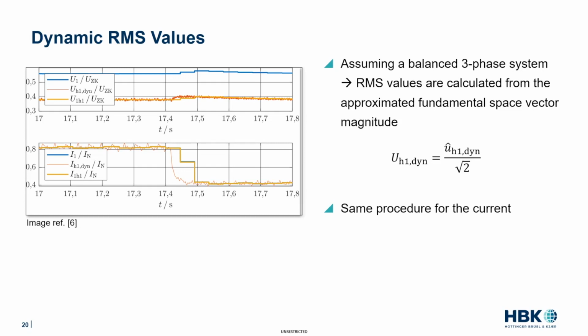Since most of the relevant active power is transferred in the fundamental for inverter-fed drives, this relates to the currents being more or less sinusoidal—recall there's only a small amount of high frequency components. So the total RMS is more or less equal to the fundamental RMS, though not exactly. The voltage, however, has a lot of high frequency components from inverter switching, so the total RMS differs strongly from the fundamental RMS.